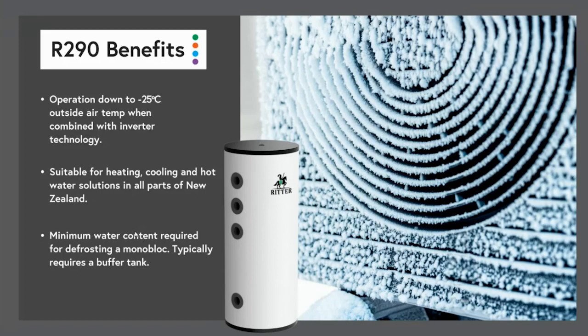So that means that an R290 heat pump can do heating and cooling and hot water all over New Zealand, including parts of Central Otago and the coldest areas of the country. R290 heat pumps, including the Vaillant, can produce 75-degree water down to negative 10. So that would mean that it's able to produce that top-end performance pretty much everywhere in New Zealand without exception.